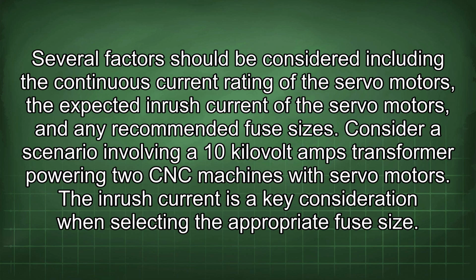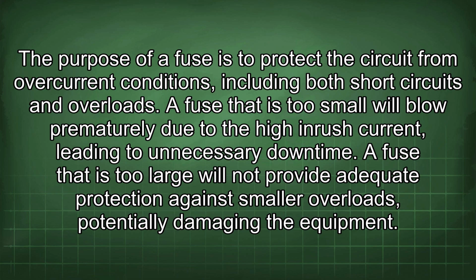Consider a scenario involving a 10 kVA transformer powering two CNC machines with servo motors. The inrush current is a key consideration when selecting the appropriate fuse size. The purpose of a fuse is to protect the circuit from overcurrent conditions, including both short circuits and overloads. A fuse that is too small will blow prematurely due to the high inrush current, leading to unnecessary downtime. A fuse that is too large will not provide adequate protection against smaller overloads, potentially damaging the equipment.